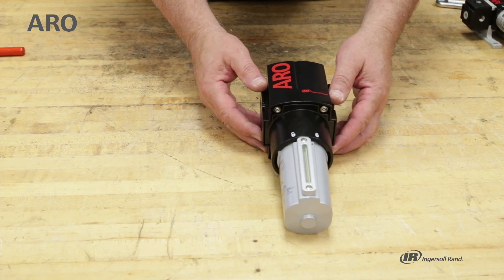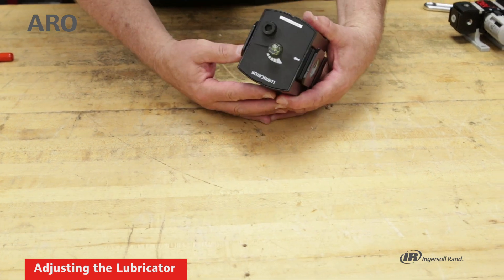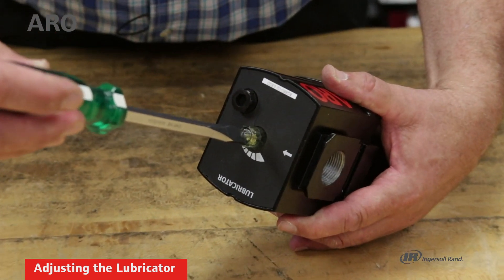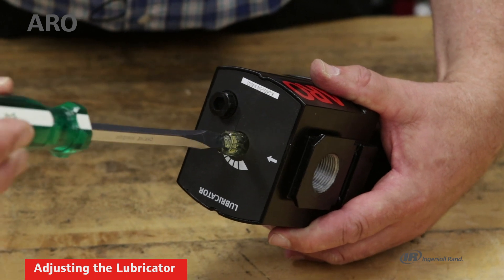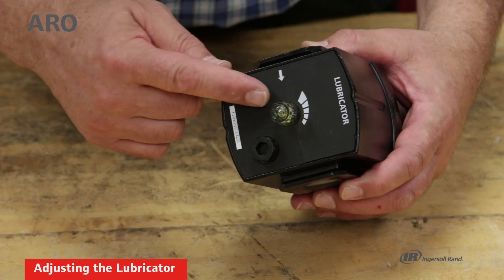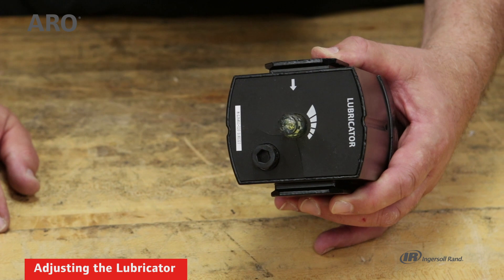For the lubricator, I want to talk about how to adjust the amount of lubricant delivered as well as filling the unit, and that's done at the top of the lubricator. You see we have the clear sight dome. Using a screwdriver and turning it clockwise will decrease the amount of lubricant dispensed, or turning it counter-clockwise will increase the amount of lubricant being put into the system. The way you'll know the setting is correct is that as a downstream device like a tool is being used, you'll actually see the oil come up into the top of the sight dome and then drop into the air supply — it'll be atomized and distributed downstream.